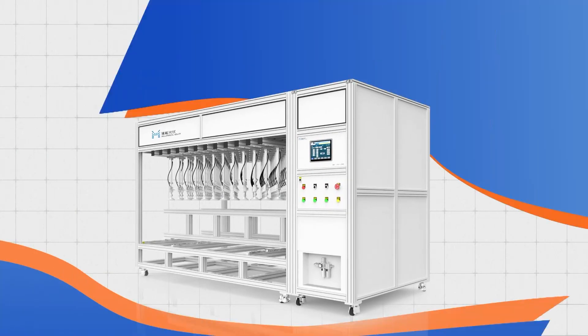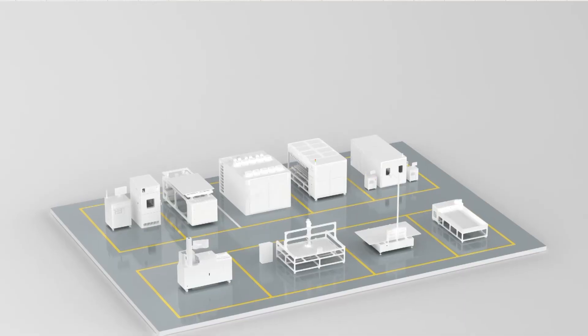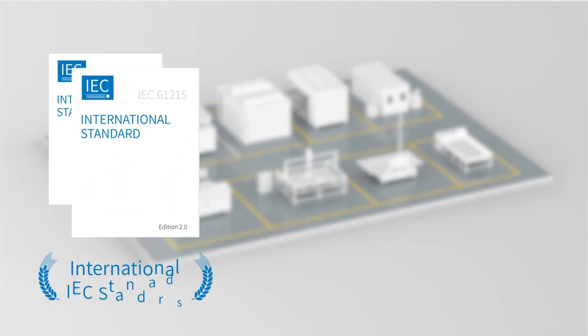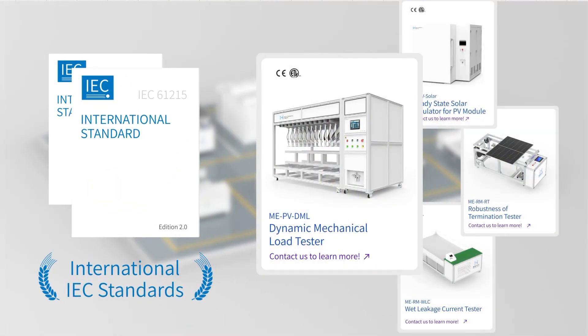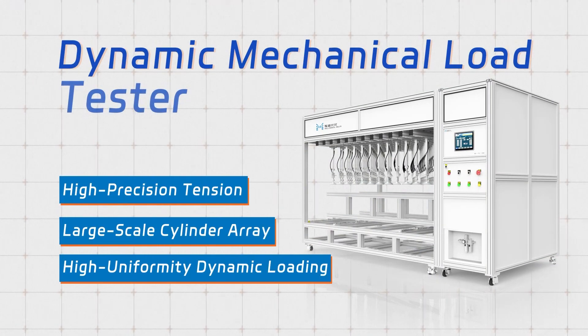Millennial Dynamic Mechanical Load Tester, compliant with standards like IEC-61215, accurately replicates diverse wind pressures in labs, offering tailored extreme wind simulations for PV modules.